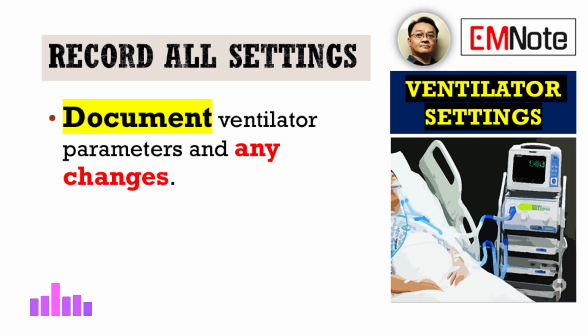Let's start with documentation then. What specific information regarding the ventilator settings and the patient's response absolutely must be meticulously recorded? You must document all ventilator parameters precisely, every single one. This includes the ventilation mode, the set tidal volume, the respiratory rate, the oxygen concentration, FiO2, and the PEEP level. This isn't just a snapshot, it's a critical record of care.